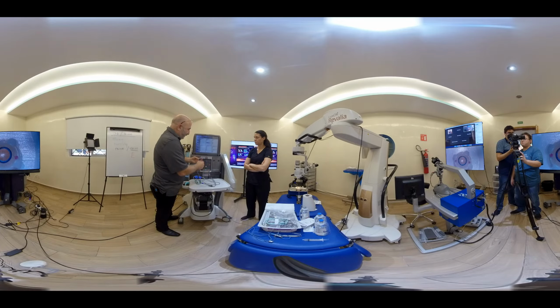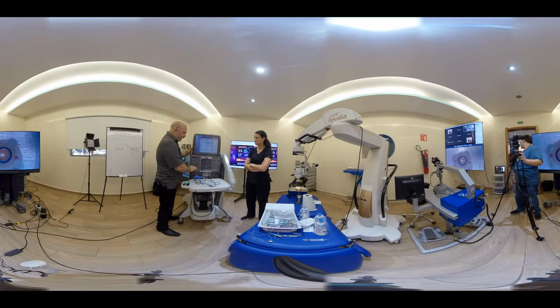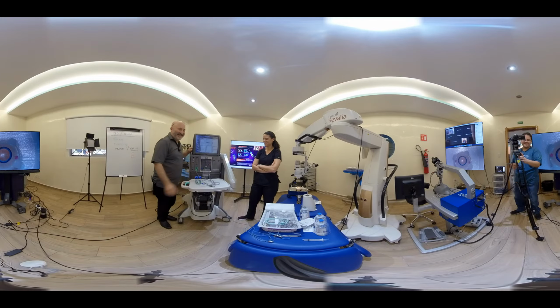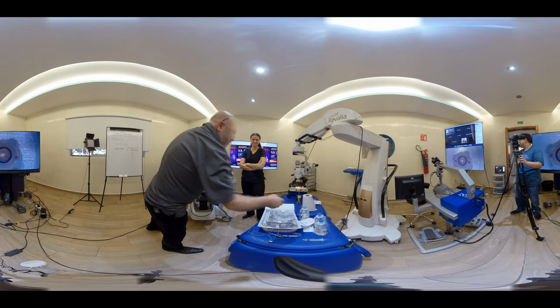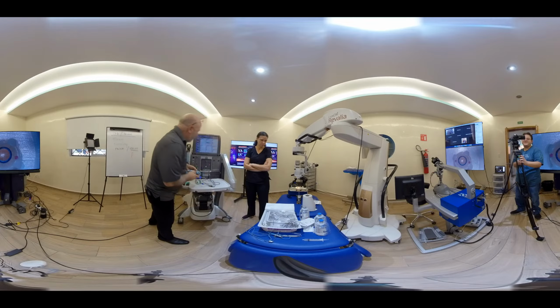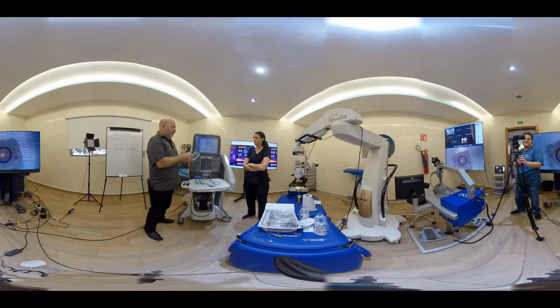So we have the vitrectomy probe, we have the black and grey pneumatic lines that open and close the port. So put that in the corresponding connectors. Then we have the aspiration, the primary aspiration line. Those of you that watch Repair That Retina would have seen last week, one of the questions was, the vit probe, what is the colour of the aspiration line? Dark blue. This is a combined pack. So what we have here is irrigation line and a secondary aspiration line. On Alcon systems for vit ret, blue is always suction, green is always irrigation or infusion.